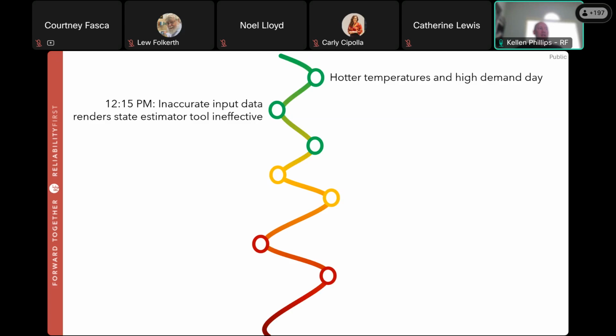In addition to the state estimator tool being down, voltage on the system was low and there wasn't enough reactive power. Capacitor banks are used to help balance this, and 4 of them were out of service on this day. So operators chose to overexcite nearby power plants, basically pushing units to their limits to get more reactive power. This was the case with a coal-fired plant on Lake Erie, East Lake Unit 5. At 1:31, East Lake 5 was pushed too hard and the unit tripped offline. This resulted in losing more voltage control and pushing other plants even harder.